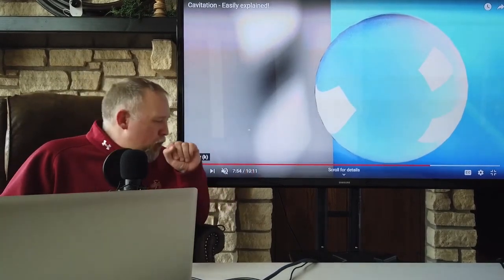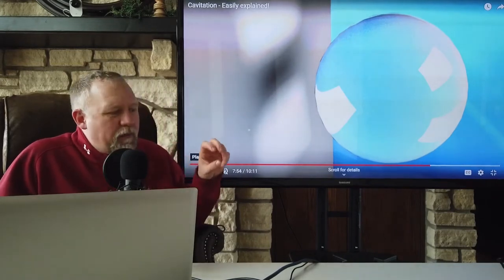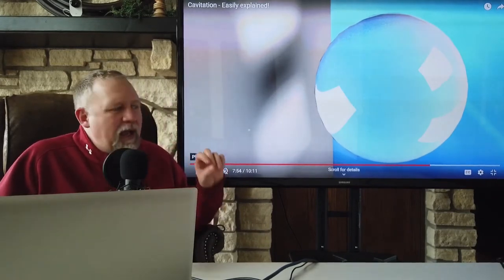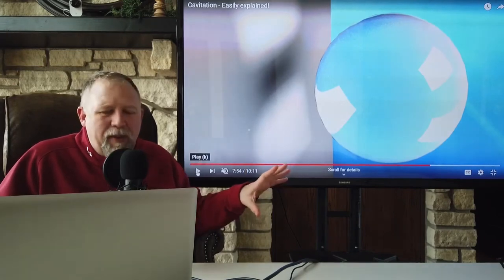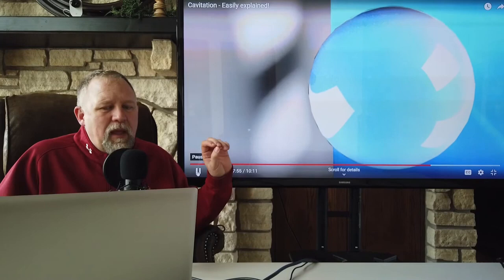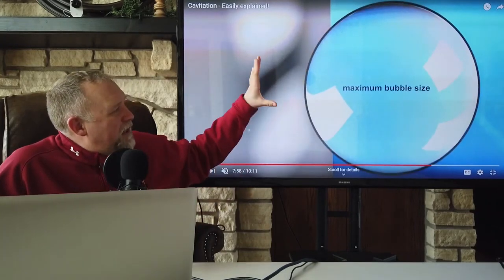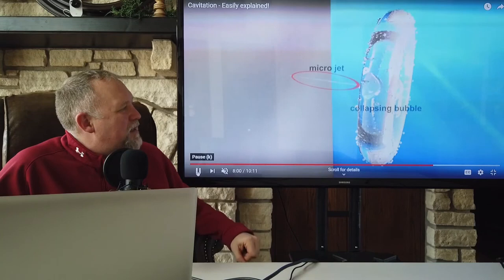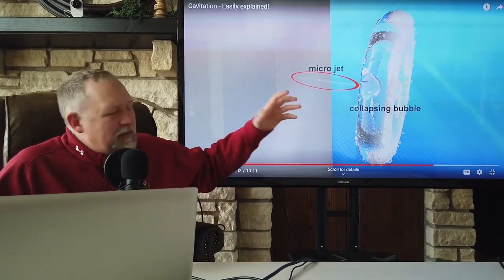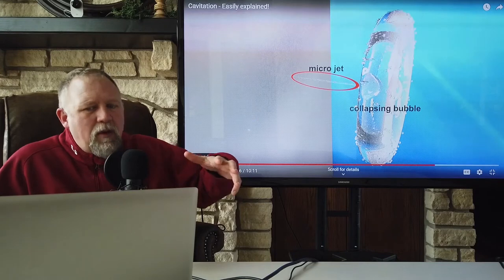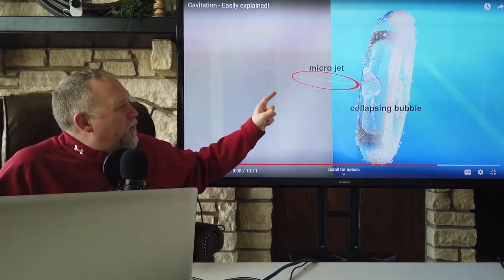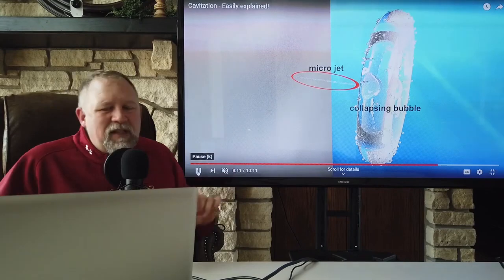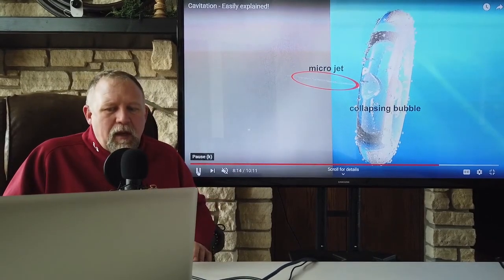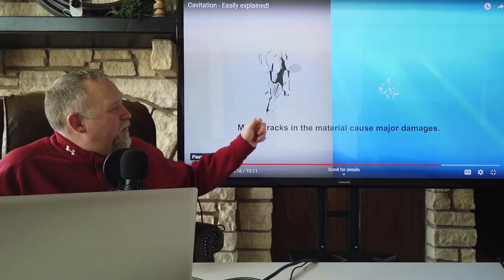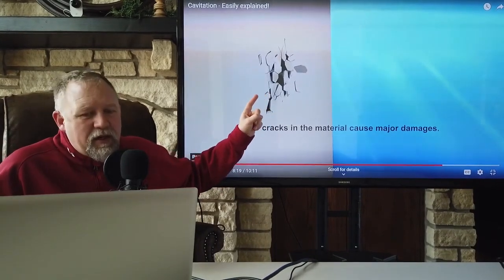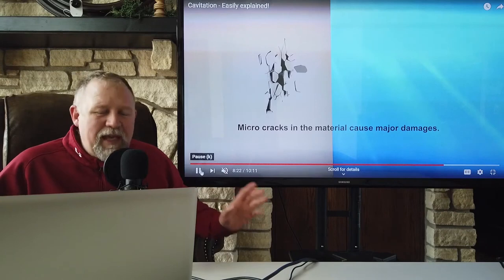As the pressure goes from the lowest point at the eye through the impeller and out to the edges of that impeller, at some point, that pressure is going to cause this bubble to increase and then drastically decrease. You'll actually get a little implosion of it and a little microjet of water screaming out from the center of that collapsing bubble. Over time, when this happens often enough, this jet can degrade the impeller material itself, even steel.